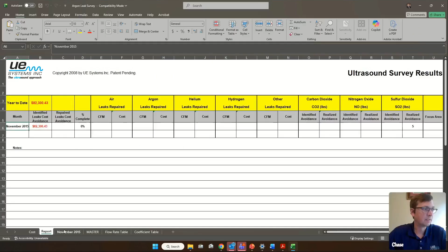We found out that the cost of their argon is basically $34.76 per 1,000 cubic feet. Walking into their shop area, we spotted essentially two leaks right away. One was on a quick disconnect right at the piece of equipment, where the tool connected in with the welding. And just downstream from it was a pipe thread leak, where someone didn't actually screw the connection on properly when putting the fitting on. These two together totaled just north of $82,000.